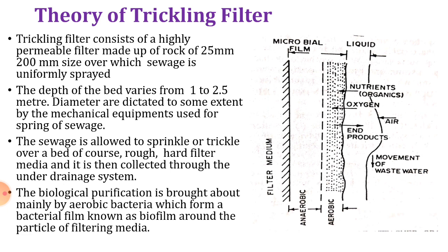So please keep in mind, it is a highly permeable rock media of size 25 to 200 mm, and over that the wastewater is sprayed. The depth of the bed varies from 1 to 2.5 meter. Diameter is dictated to some extent by the mechanical equipment used for spraying of sewage. The sewage is allowed to sprinkle or trickle over a bed of coarse, rough, hard filter media, and it is then collected through the under drainage system.